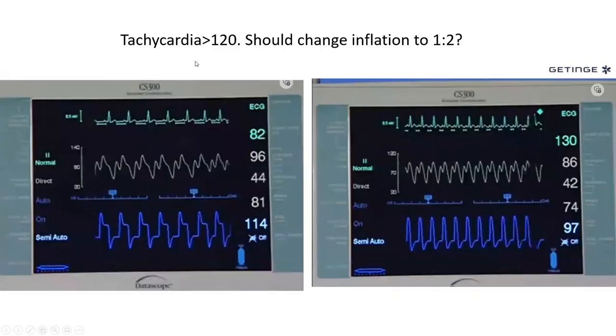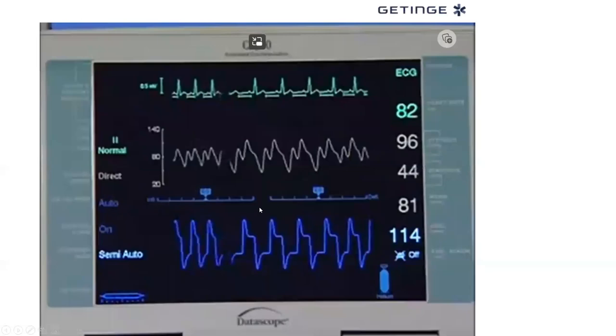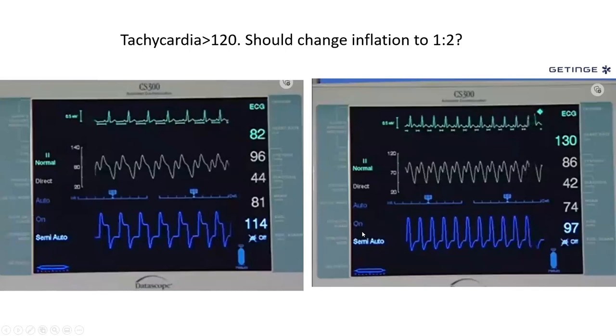This brings that common question: if you're tachycardic over 120, should you change your inflation to 1 to 2? So this is a patient. He's gone from a rate of 80 to 130. And you can see how his waveform, the augmentation, this is the augmentation. This is his systolic pressure, and this is the augmented pressure. You can see that the augmentation attenuates as he gets tachycardic. As here, the augmentation attenuates as you get tachycardic. So a lot of people think, and still think, that you should do 1 to 2 to improve the augmentation. That's a wrong idea. I please want to erase that very erroneous thought.